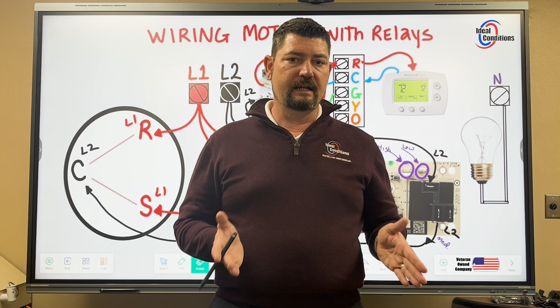Now, I told you that I would cover the efficiency on this. There's a 60-second off delay. The moment we lose G from the thermostat, so G is no longer here, there's a 60-second, 65-second countdown. Let's say the unit comes on and cools for 10 minutes, then shuts off for about 10 minutes, and then comes back on for 10 minutes. In 1 hour, it ran 3 times. We don't care about the run time. We care about how many times it turned off. Well, that's 3 times per hour.